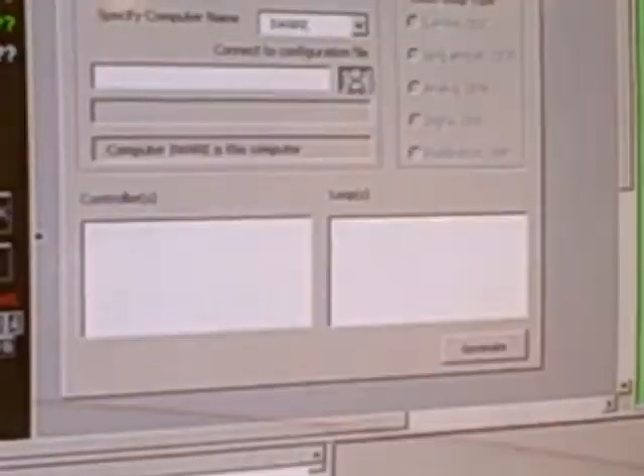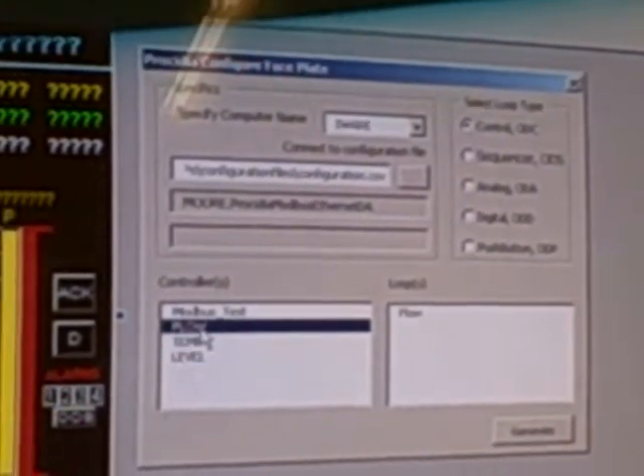So now I'm going to double-click on the object, and that brings up a faceplate configuration window. It says I need to connect to a configuration file. So I click the Browse button here, and under Configuration Files there's only one file I can click. This was generated by the OPC database configuration utility that we ran earlier. I open up that configuration file, and it shows three controllers — flow, temperature, and level — that it recognizes. I'll just pick any one of those.